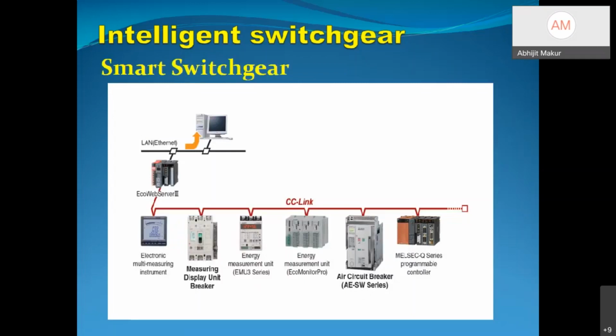Intelligent switchgear is the form of switchgear that we have now. Earlier, all the switchgears had a separate module for switchgear, a separate module for protection and sensing equipment, and then a relay module which combined the protection features. These separate modules did not have any communication module, but as we move ahead, without a communication module it is not possible to maintain the system. As the number of consumers we are required to feed from the same sources has increased, and there are issues in every case, you need communication between each module so that any issue can be analyzed and located.